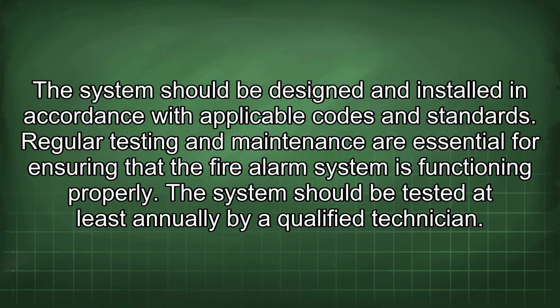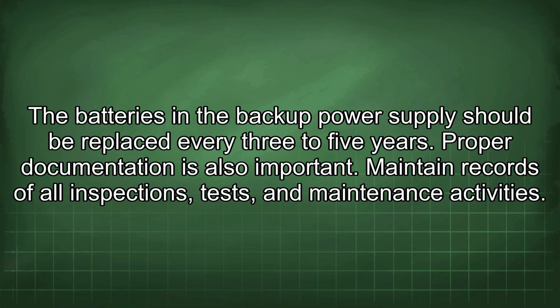Regular testing and maintenance are essential for ensuring that the fire alarm system is functioning properly. The system should be tested at least annually by a qualified technician. The batteries in the backup power supply should be replaced every 3 to 5 years. Proper documentation is also important.